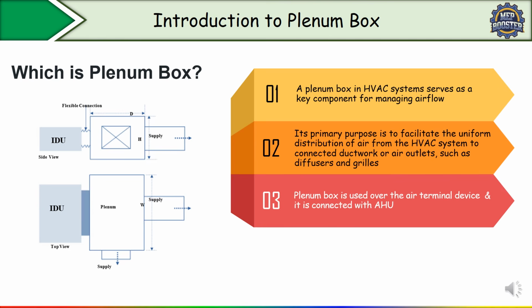So a plenum box is used over the air terminal device and it is connected with AHU. Either you can use the plenum box over the air terminal device, for example a diffuser, or it is also connected with AHU or FCU. Here in this figure you can see the plenum box is connected with the indoor unit, either an FCU or AHU. See, the side view is given. When you see the plenum box from the side view, the height and depth of the plenum box are visible, and from the top view, the width and depth are visible. Correct? Now you have to connect the supply duct.